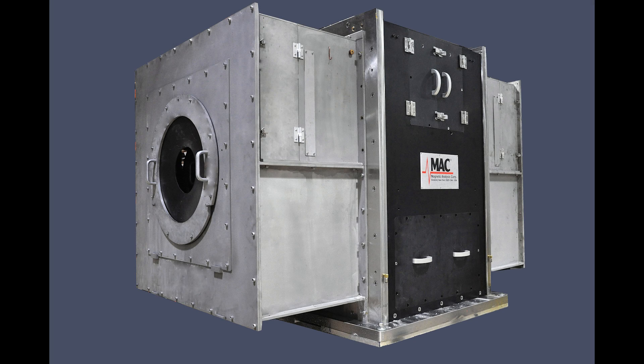The third tester in the system is the UT 500 mm, which is a 24-channel ultrasonic rotary with up to 48 transducers. This unit tests for longitudinal and transverse defects, as well as lamination and wall thickness measurement.